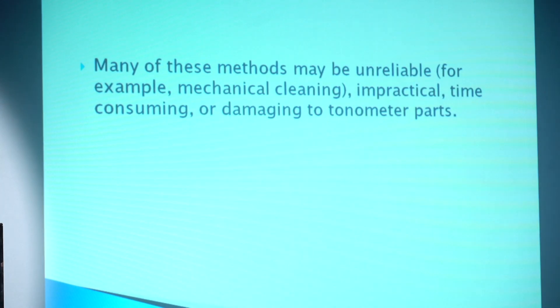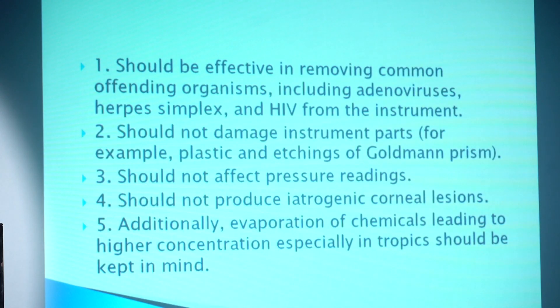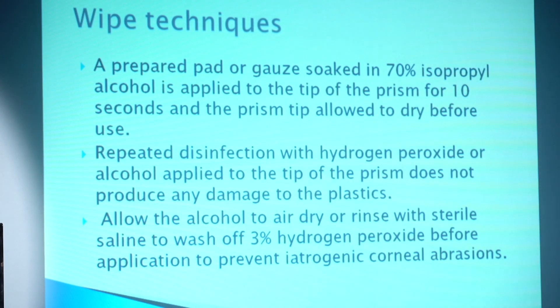The cleaning method should be effective in removing common offending organisms such as adenovirus, herpes simplex, and HIV. It should not damage instrument parts such as the plastic and etchings of the Goldmann prism, and should not affect pressure readings. For the wipe method, a prepared pad or gauze soaked in 70% isopropyl alcohol is applied to the tip of the prism for 10 seconds, then the prism tip is allowed to dry before use.